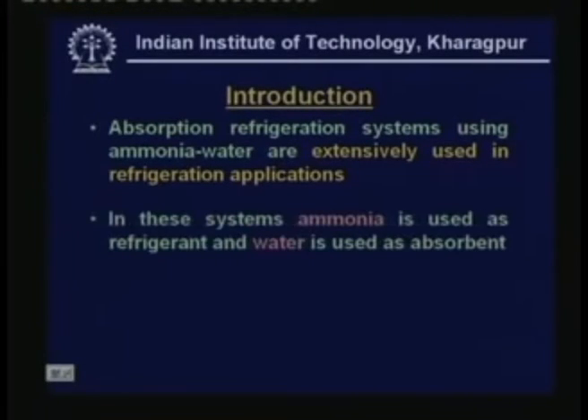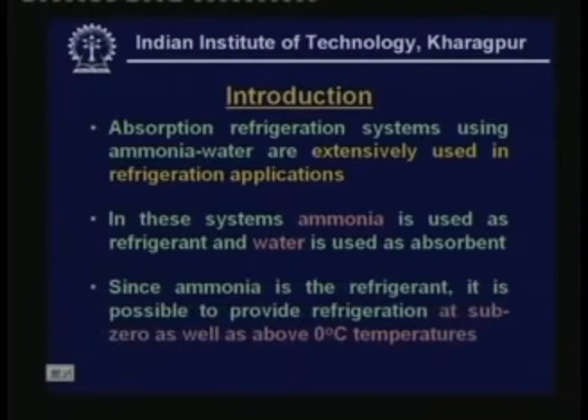As the name implies, in absorption refrigeration systems using ammonia water, ammonia is the refrigerant and water is the absorbent, and they are extensively used in refrigeration applications. Since ammonia is the refrigerant, it is possible to provide refrigeration at subzero as well as above 0°C temperatures. Ammonia water systems are much more versatile than water lithium bromide systems because you do not have the problem of temperature restriction.